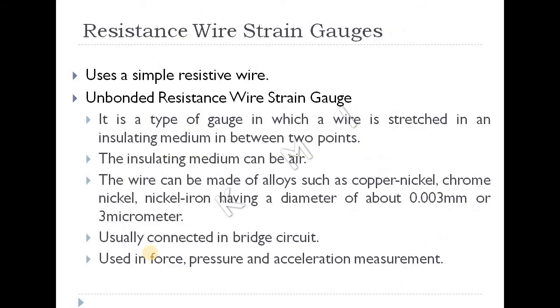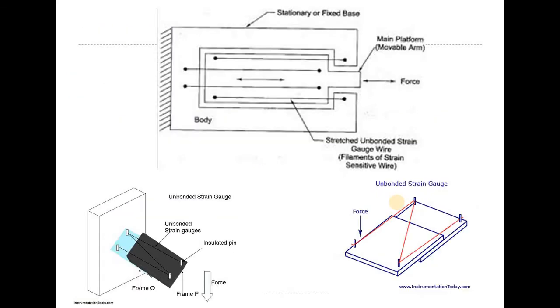The wire used in unbonded strain gauge is made of copper-nickel, chrome-nickel, or nickel-iron. The insulating medium is air, so it is unbonded — the wire is not directly attached to the surface.